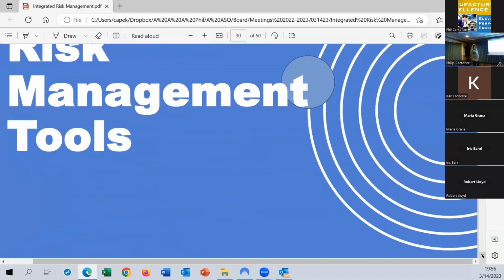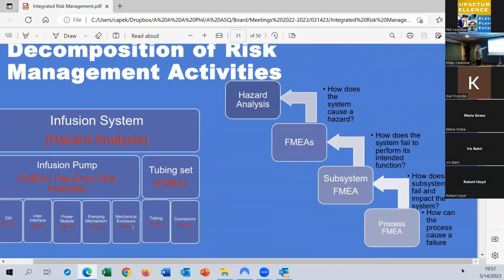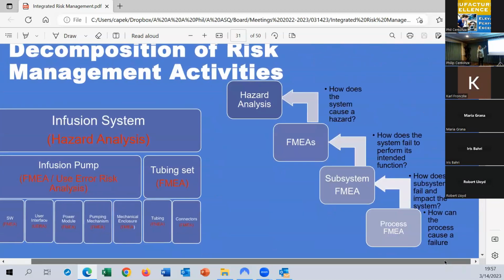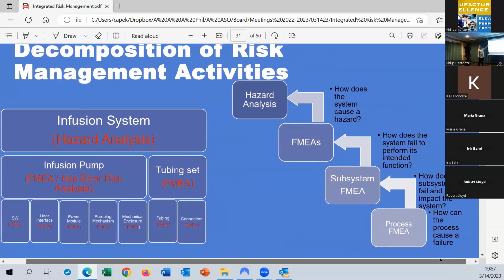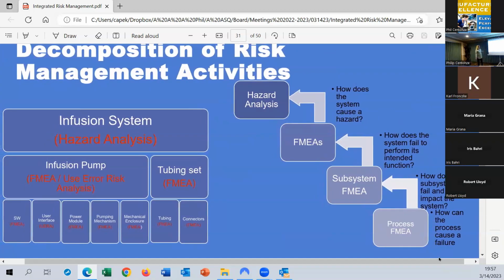All right, so let's talk about some risk management tools. So we just said we're talking about the system level, right? The risk really has to be mitigated at the system level. So the system has different components, right? Like an infusion pump, you have the infusion pump and the tubing set that allows the medication to get to the user. Well, I'm going to mitigate at the system level because no matter what I do here, I might be able to reduce the likelihood that these items fail.